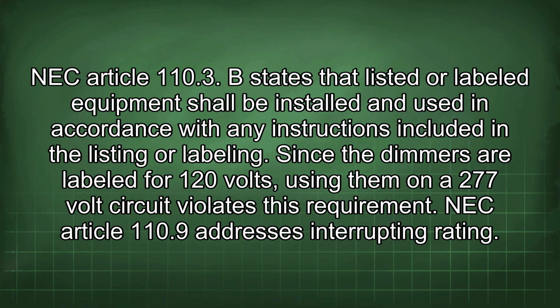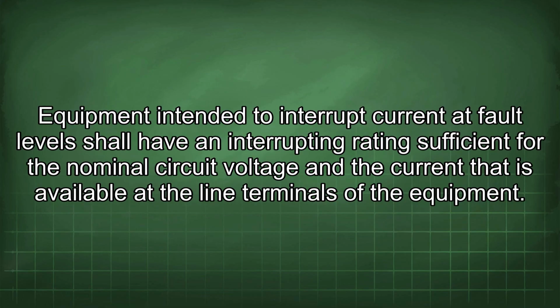NEC Article 110.3(B) states that listed or labeled equipment shall be installed and used in accordance with any instructions included in the listing or labeling. Since the dimmers are labeled for 120 volts, using them on a 277-volt circuit violates this requirement. NEC Article 110.9 addresses interrupting rating. Equipment intended to interrupt current at fault level shall have an interrupting rating sufficient for the nominal circuit voltage and the current that is available at the line terminals of the equipment.